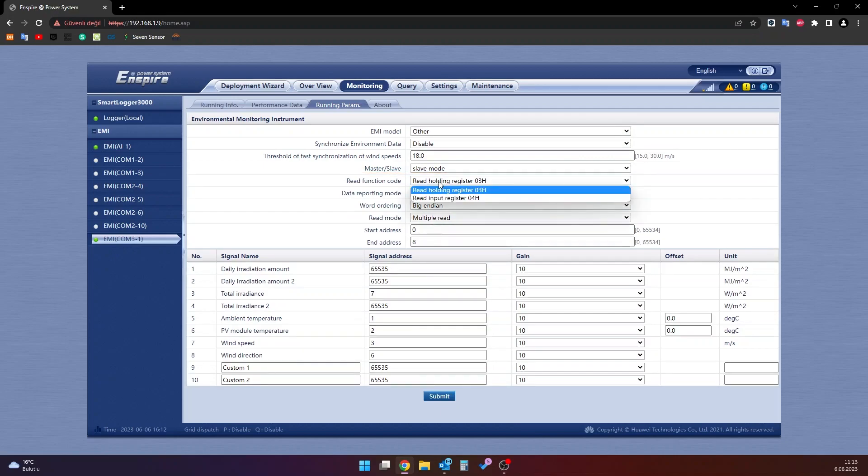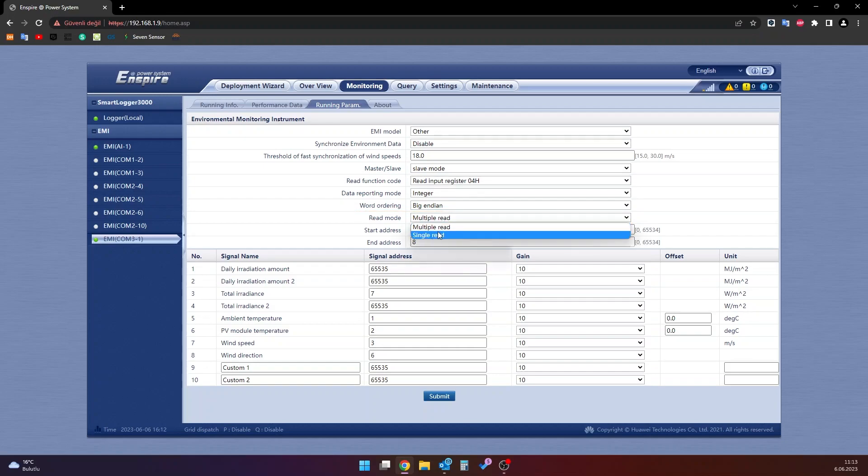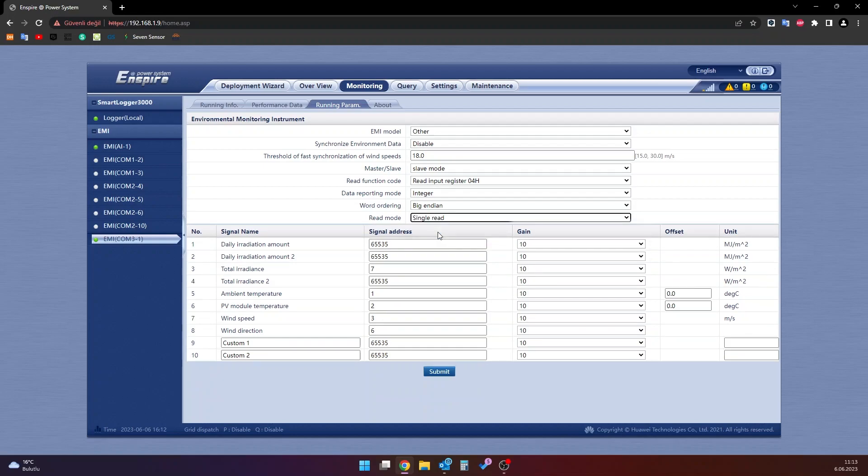For the read function code section, this section must be selected according to the type of register we want to read, input or holding. In data reporting mode section, select integer. In the word ordering section, choose big endian. In the read mode section, choose single read.